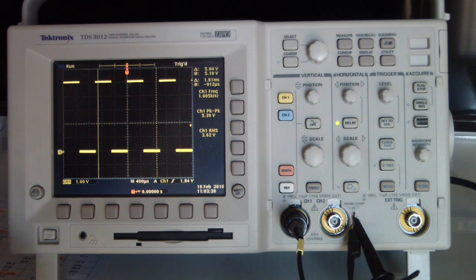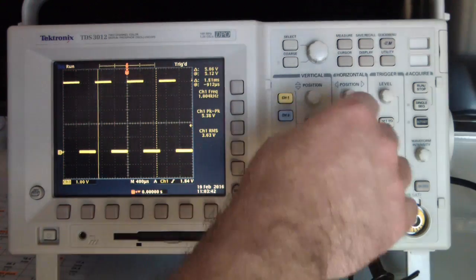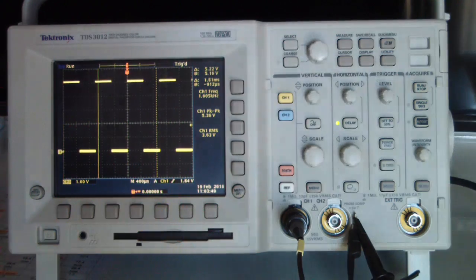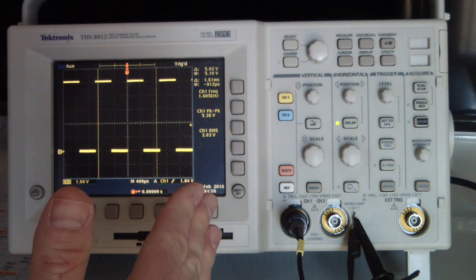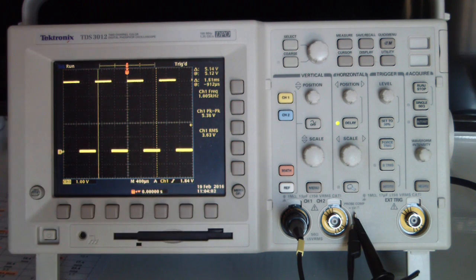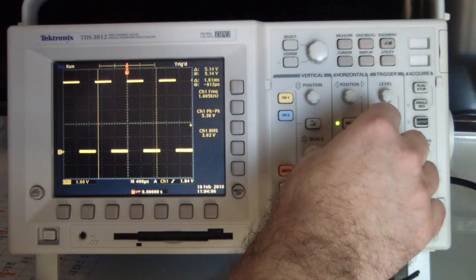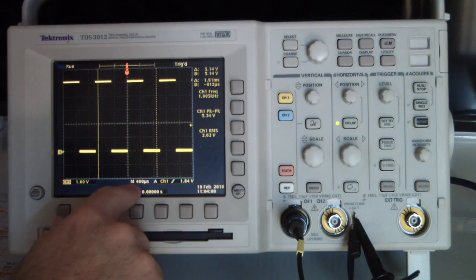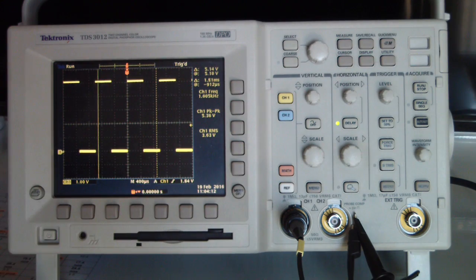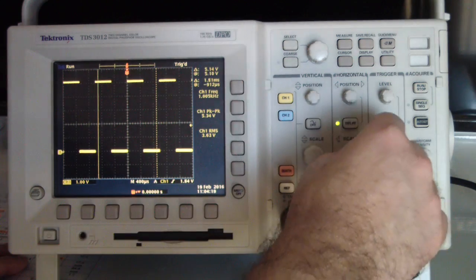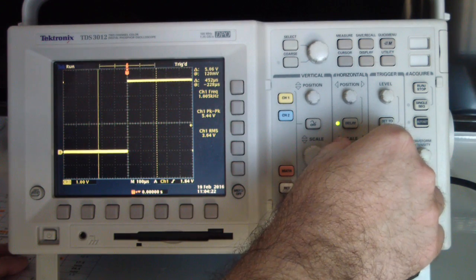We should be able to see the maximum, the best picture that we want to see. We can change it and move it around this point. Also, we have the horizontal scale, which changes the square on the x-axis, the time per square. Okay, so let's see it. Now it is calibrated to 400 microseconds per square on the x-axis. And if I change it to a lower value, I will see the signal more open.